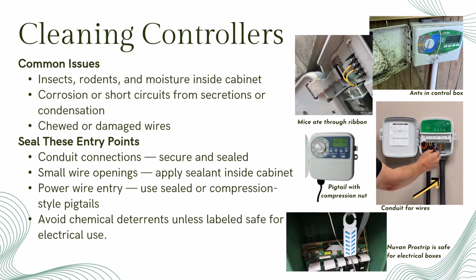They can become home to ants, wasps, roaches, or even small rodents. These pests can corrode circuit boards, chew through wiring, and create safety hazards for anyone opening the cabinet. Even moisture from condensation can shorten the lifespan of the electronics inside, so keeping the cabinet clean and sealed is essential. After clearing out debris or pests, seal every entry point that allowed them in.